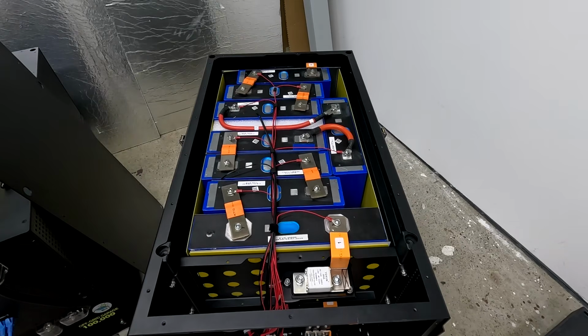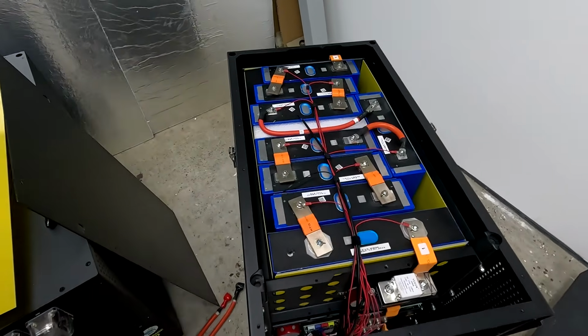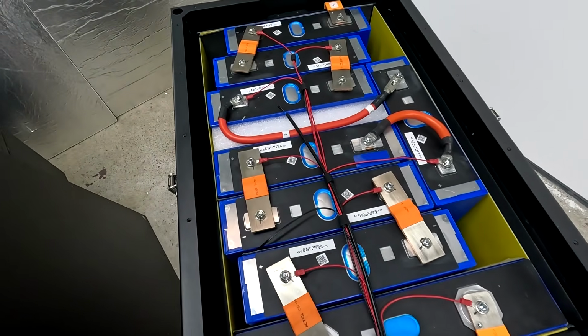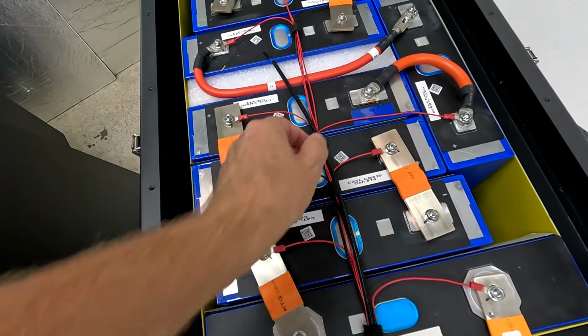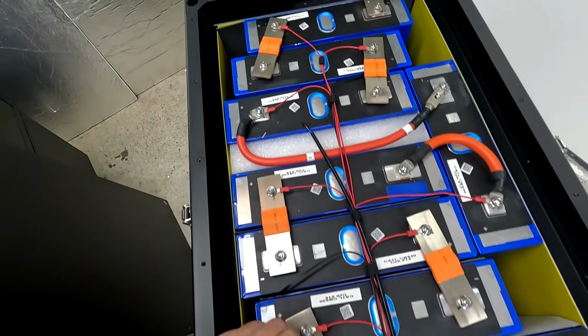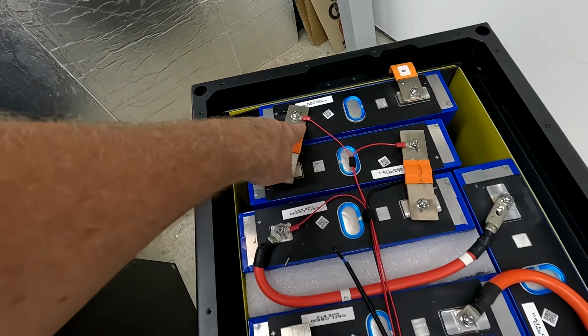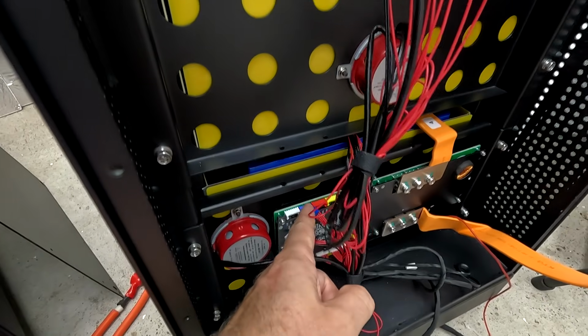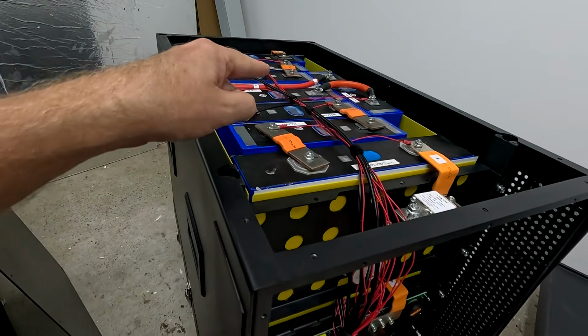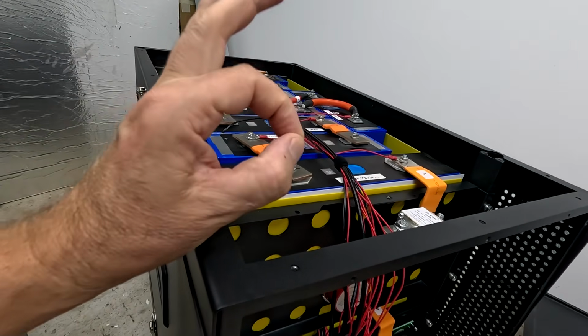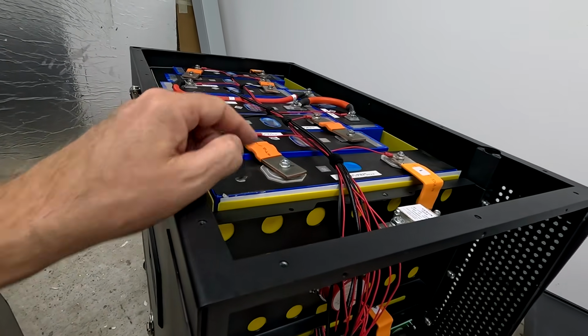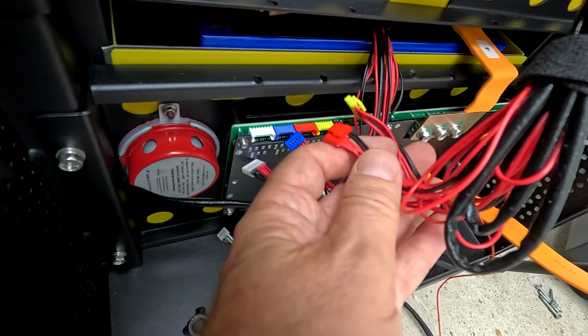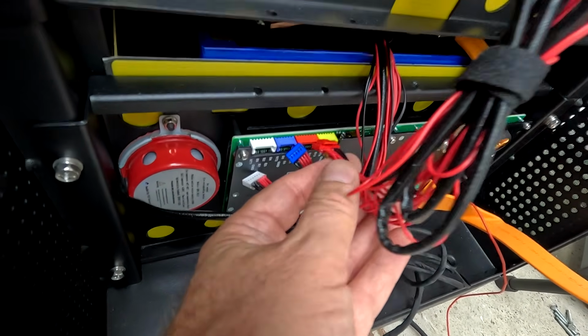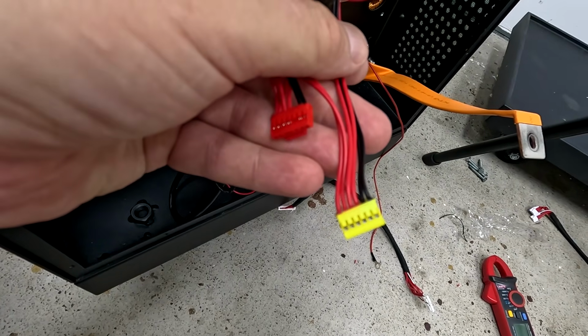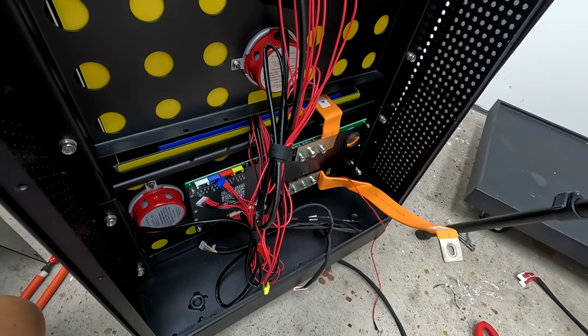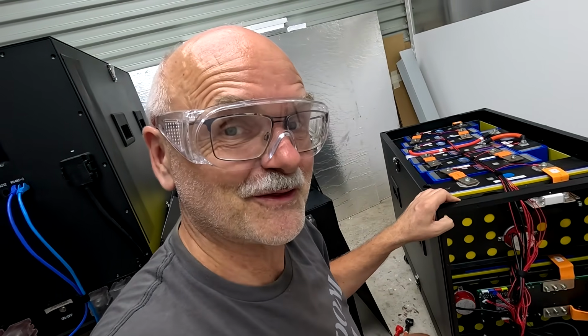Alright my friends, there's the top compartment ready, cabled, torqued, marked, checked. I've done pretty much the same as in the bottom compartment, so I used a bit of Velcro to organize the balance cables here. And this furthest away cable was just long enough, because from the BMS we have to go up all the way and then across the whole length of the battery box. So thankfully Yixiang delivers these long cables with their BMS, and it all worked out. And now we can also see what the colors are for. Okay, last thing is to check these balance cables here for the right voltage order, and then we can plug everything together and turn on the Frankenstein battery for the very first time.